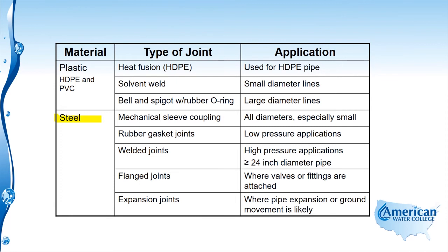Next is steel pipe. There are many different joints for steel. The mechanical sleeve coupling can be used on all diameters but is more typically used on smaller diameters. The rubber gasket joint is used in low pressure applications. Welded joints are used in high pressure applications and on pipe diameters of 24 inches or greater. Flange joints are used where valves or fittings are attached to the steel pipe. Finally, expansion joints are used where pipe expansion or ground movement is likely. You want to remember these different types of joints for the different types of pipe material.